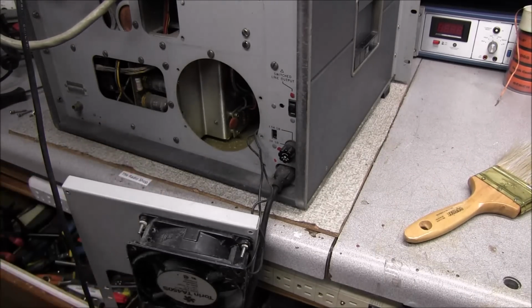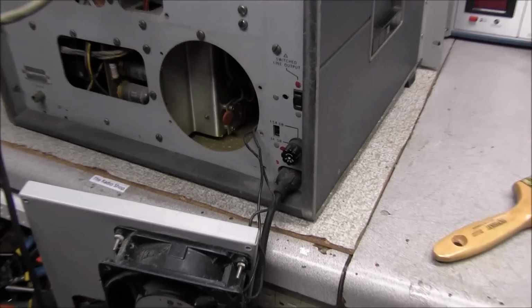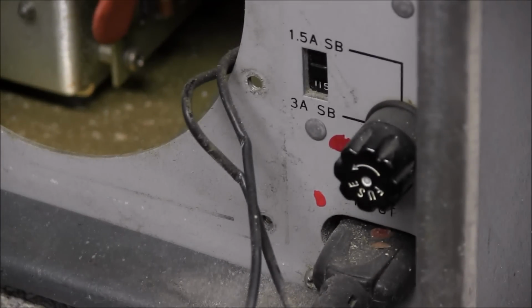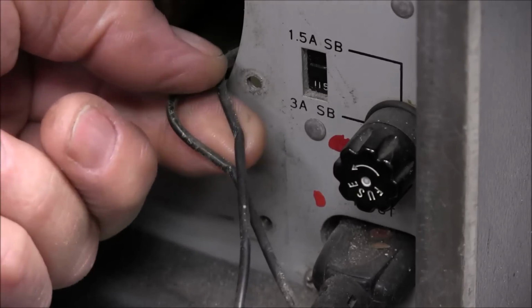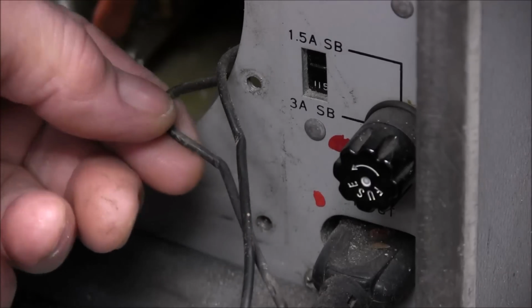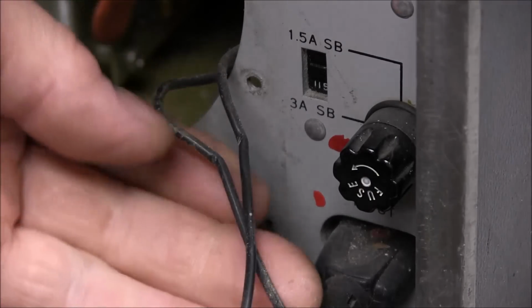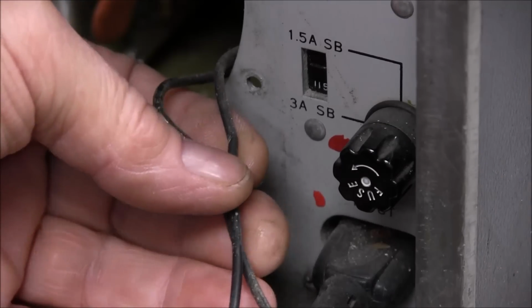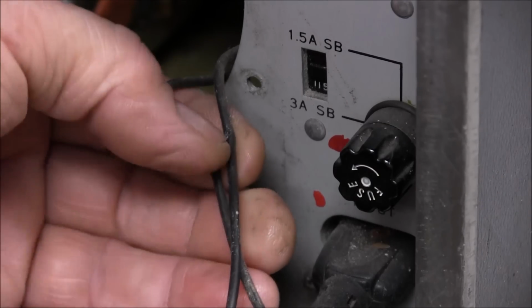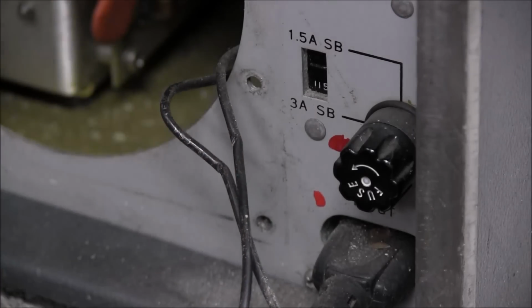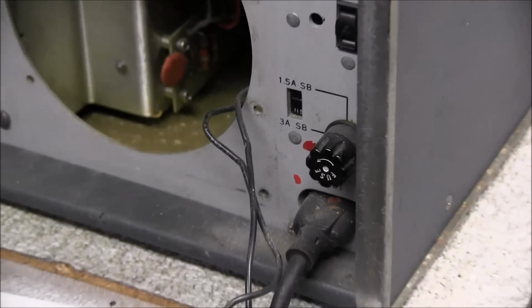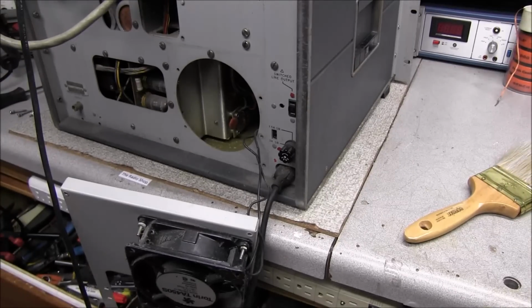I pulled this cover off, and sure enough, as you can see, it has really bit down on those wires real good, and it does look like it's cut right down to the wire itself, right through the insulation. Not a good thing. This is why you do not run wires like that. That can cause all kinds of bad things to happen.